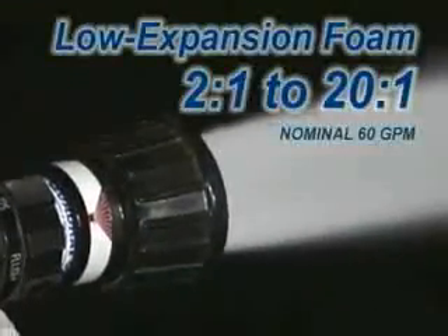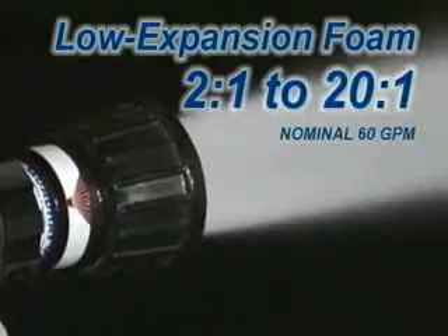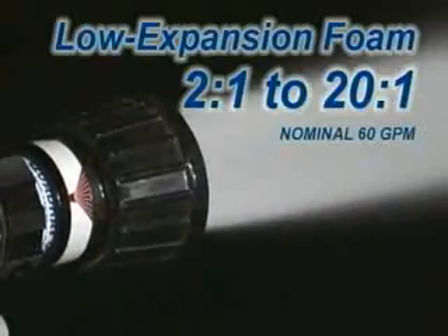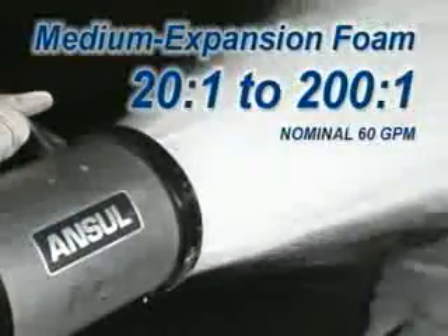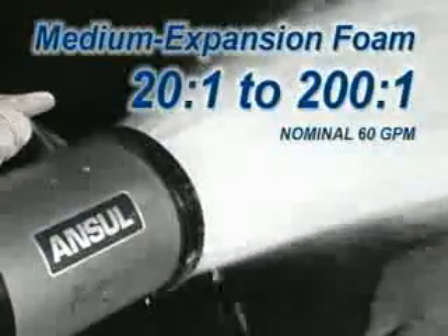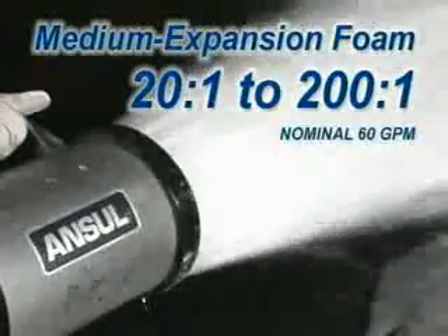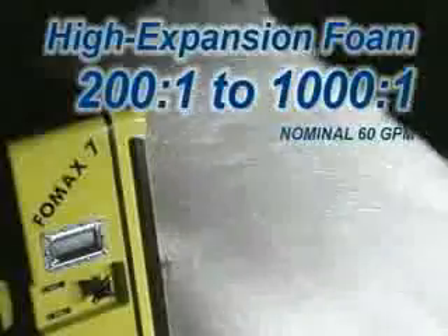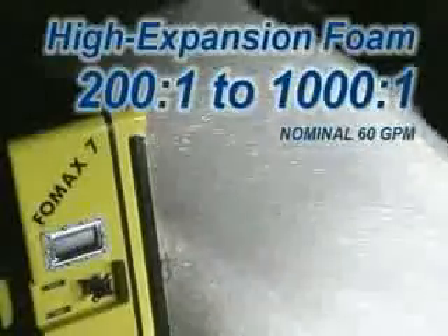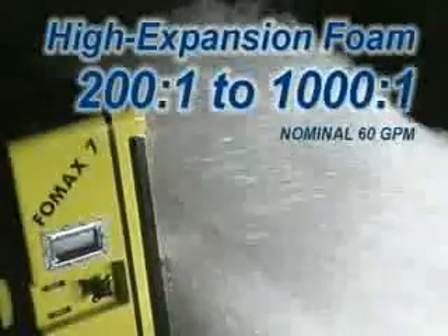Low expansion foams have expansion ratios ranging from 2-to-1 to 20-to-1. Medium expansion foams range from 20-to-1 to 200-to-1. While the ratios for high expansion foams range from 200-to-1 to approximately 1,000-to-1.